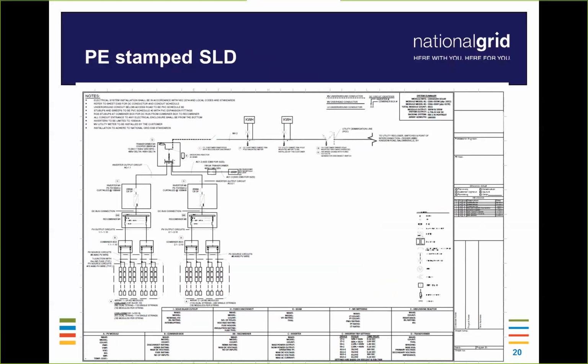Now, what's important on the drawing is anything that would be of interest to the utility. So with that being said, in this example you're going to have an overhead primary service, a three-phase gang-operated switch. That would be of interest, so we would want to see that type of device on the drawing. If there is a protective element that's required by us, such as your primary overcurrent protective device, that item should be shown on the drawing. Any protective relaying elements should be represented on here, and their instrumentation transformers that feed into those elements are something we would require shown on the drawing.